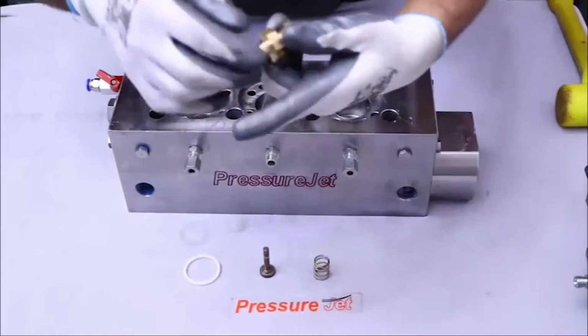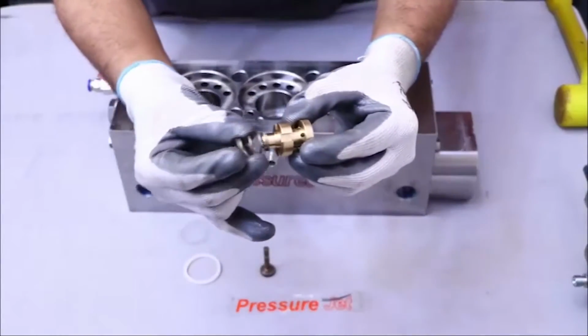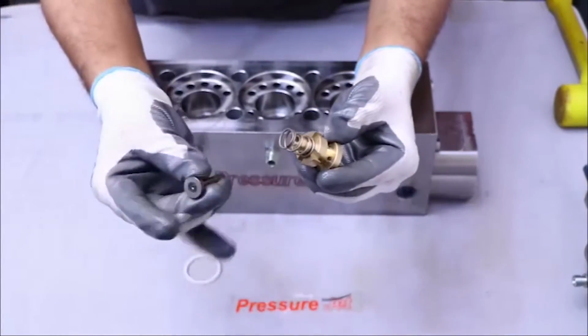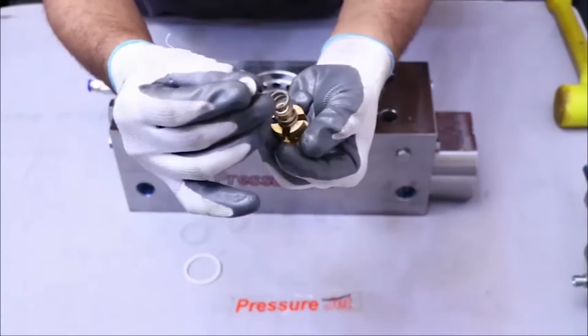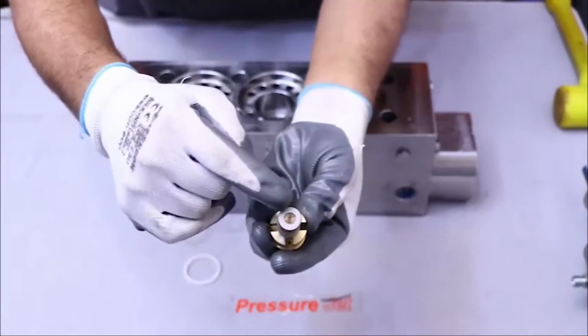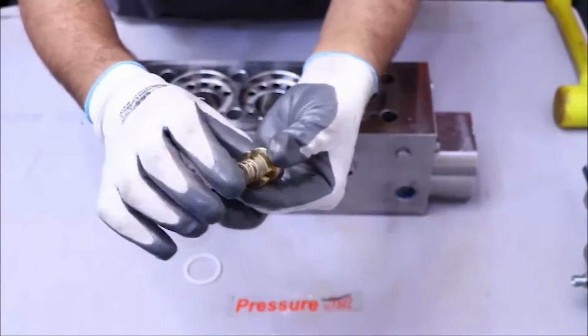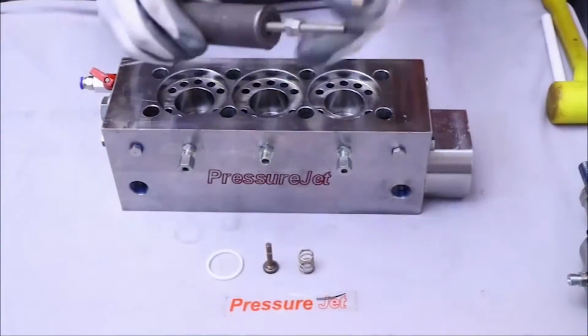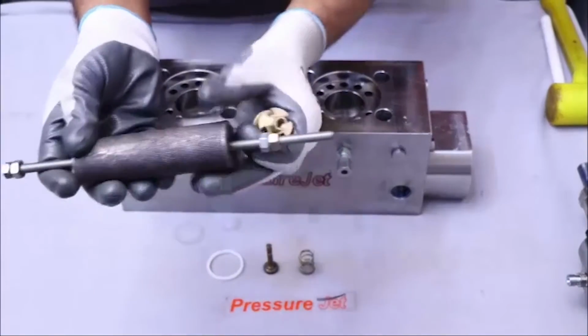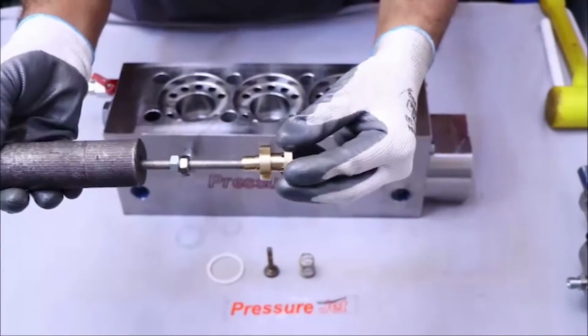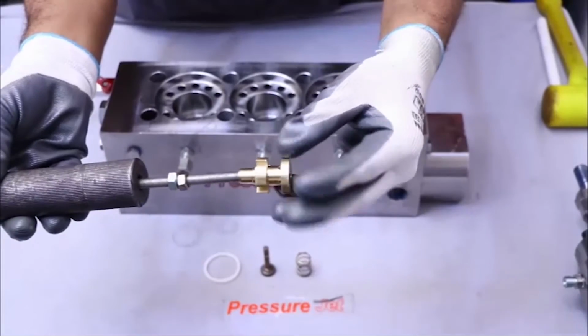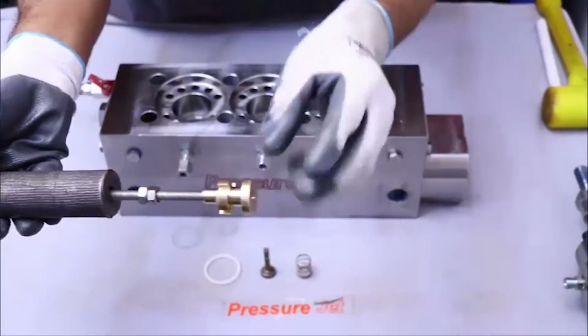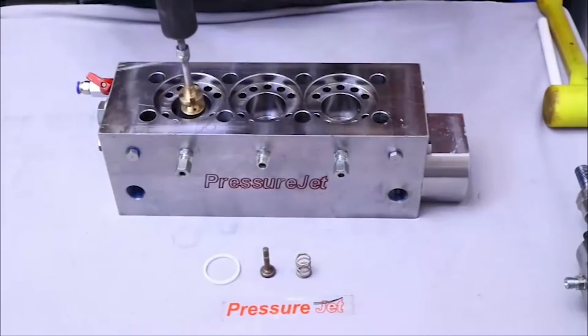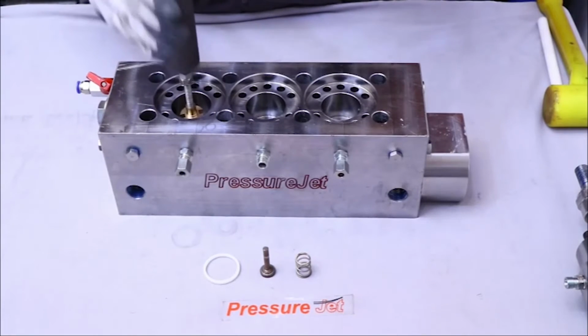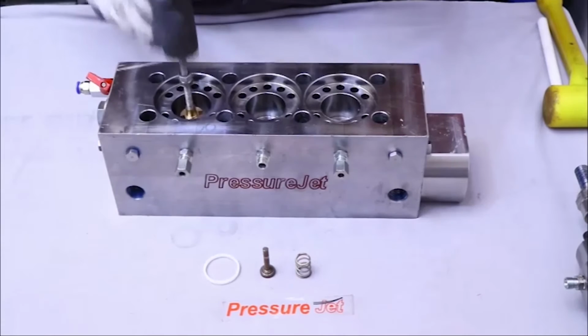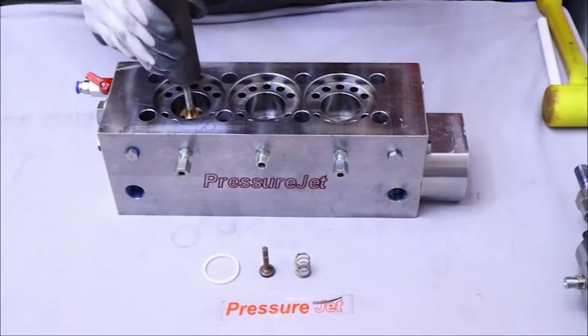Assemble the discharge valve guide, and check that it works freely. Also check the stiffness of the helical spring. Now start assembling the discharge valve guide using the discharge valve guide puller. Screw the discharge valve guide onto it. Place the discharge valve in its position. Then push it and fix it with the help of the discharge valve guide puller.